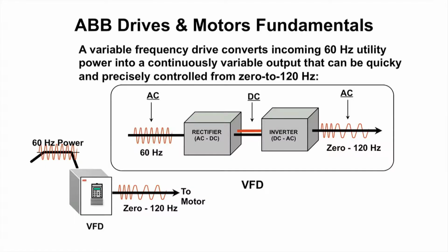So to that diagram, if you took 230 volts single phase, you could run a 3-phase motor. Absolutely. The question was, if we were to take in 230 volt single phase power coming in here, could we run a 3-phase motor here? Yes. Most modern VFDs are set up to be able to take in single-phase power and spit out 3-phase power.